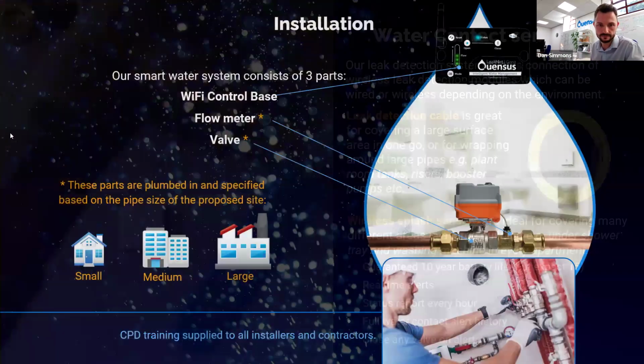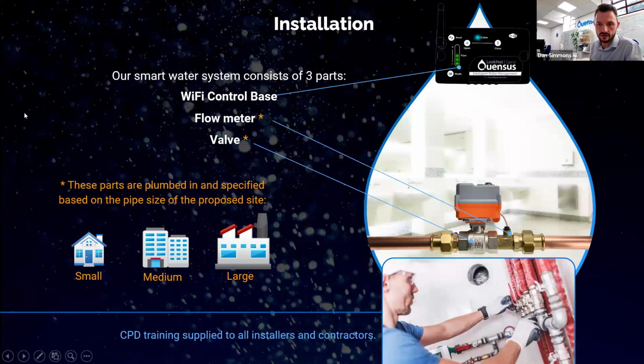So how does it get installed? If it's a retrofit, then what we do is we turn the water off, cut the pipe, and plumb the flow meter and valve in.